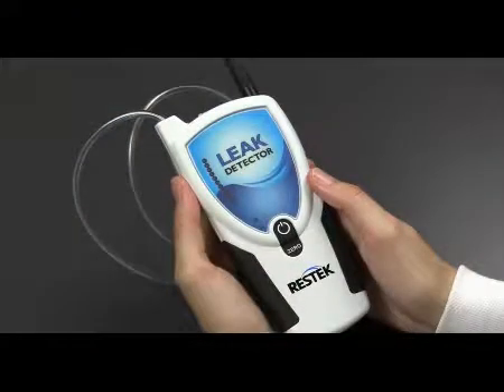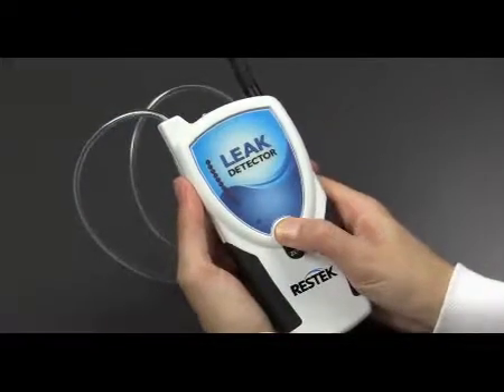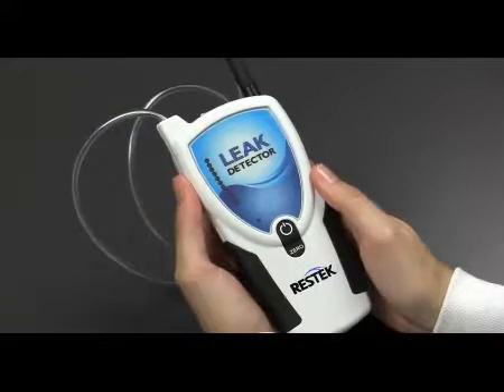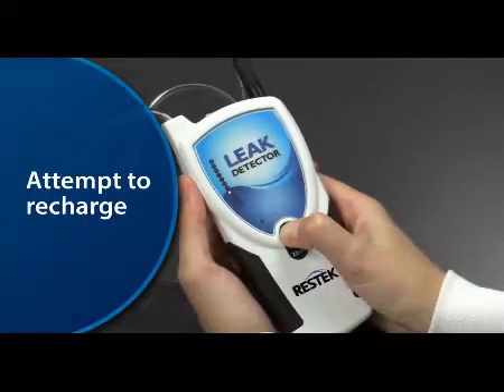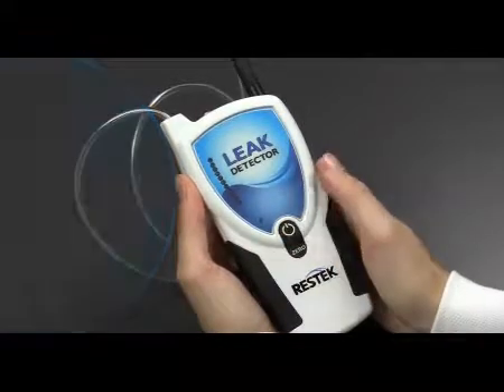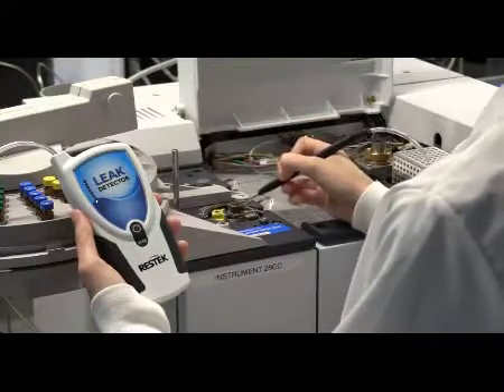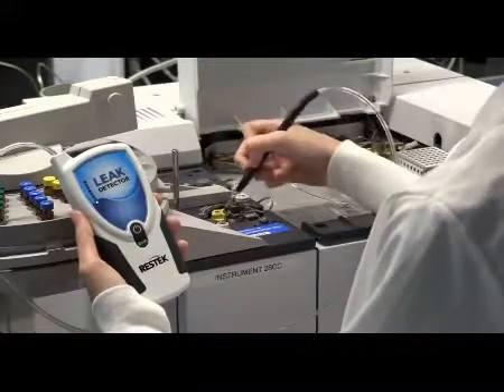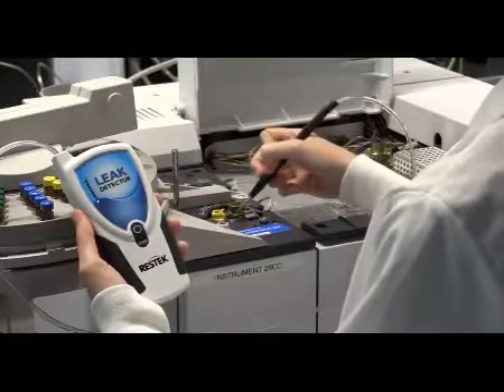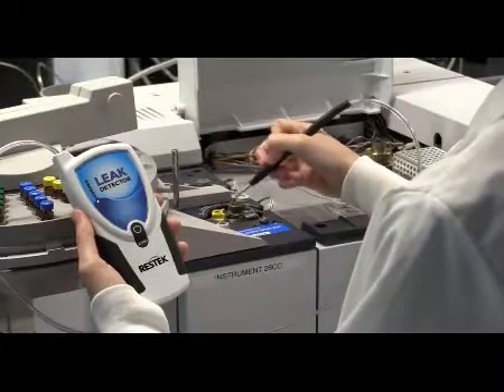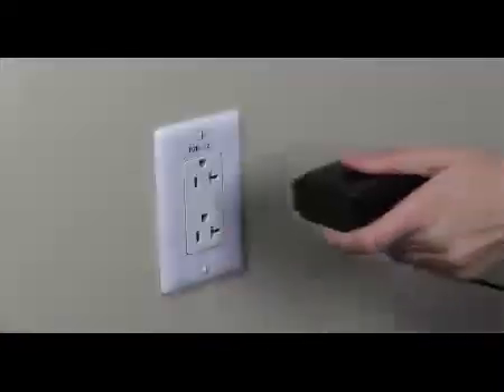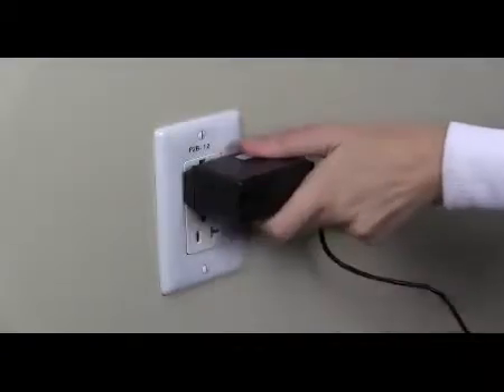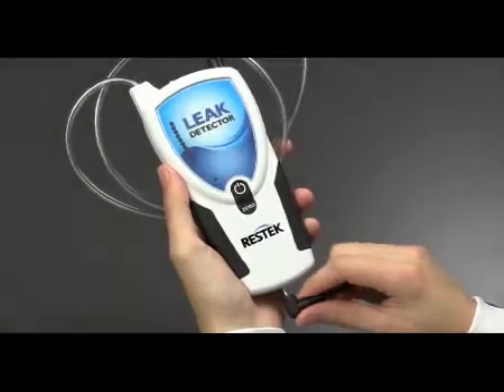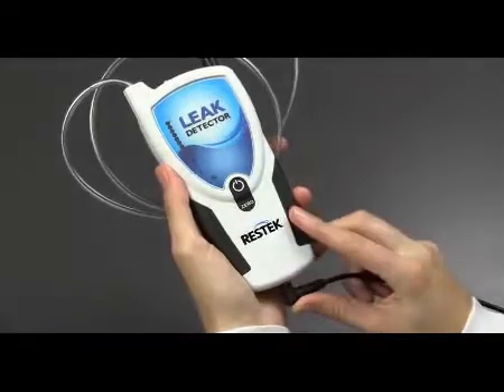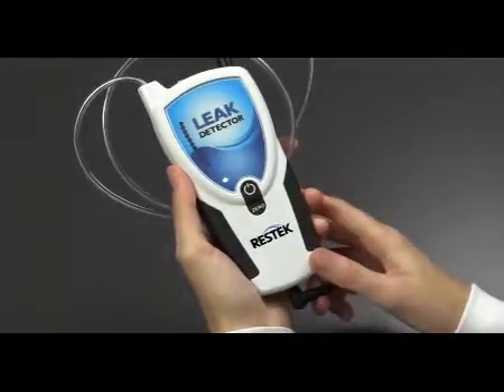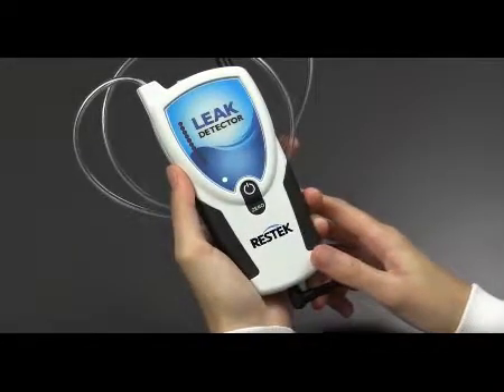If no LEDs light after attempting to turn the unit on, the battery may be fully discharged. If this happens, attempt to recharge the unit. The Restek electronic leak detector uses a lithium-ion battery because it provides a long life on each charge, but battery life is dependent on use. We recommend that you charge your leak detector at least once every 3 to 4 months.